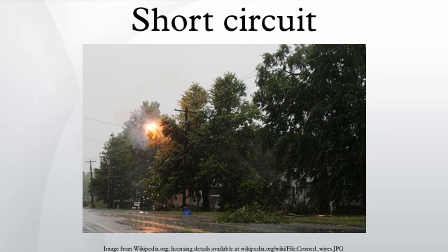In an improper installation, the overcurrent from a short circuit may cause ohmic heating of the circuit parts with poor conductivity. Such overheating is a common cause of fires. An electric arc, if it forms during the short circuit, produces a high amount of heat and can cause ignition of combustible substances as well. In industrial and utility distribution systems, dynamic forces generated by high short-circuit currents cause conductors to spread apart. Bus bars, cables, and apparatus can be damaged by the forces generated in a short circuit.